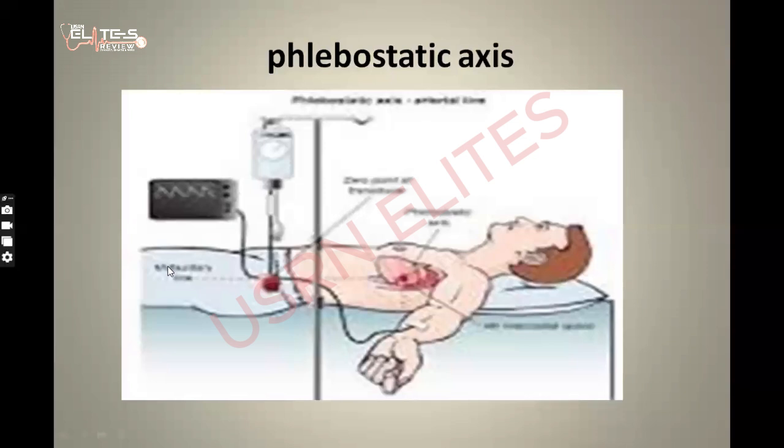So when you zero, it gives you a waveform to indicate that it has picked the signal from the artery. And then you close it, you open to the patient, and then it will be able to check the blood pressures. Most of the times it is a continuous monitoring, sort of. But once in a while, when the patient moves or something, it can dislodge, and then you have to go through the process of zeroing again. So that's it.